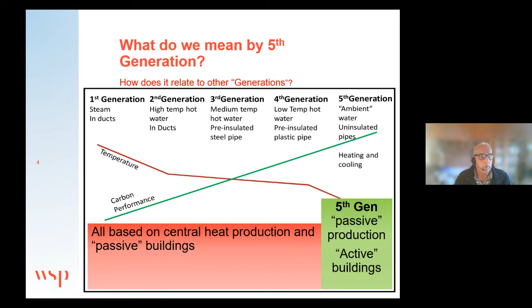So the first thing is very low temperature. There are 2 main areas you could talk about here. One would be ambient, in the normal 10 to 20 degrees centigrade range - so you might be taking water out of a lake or the sea, or using a ground loop. The other type would be recovered heat, perhaps heat recovered from data center cooling or similar. There you start to see you could think about a heating and cooling system, taking heat out at 20 or 40 degrees and maybe rejecting it in at 20 to 40 degrees as well.